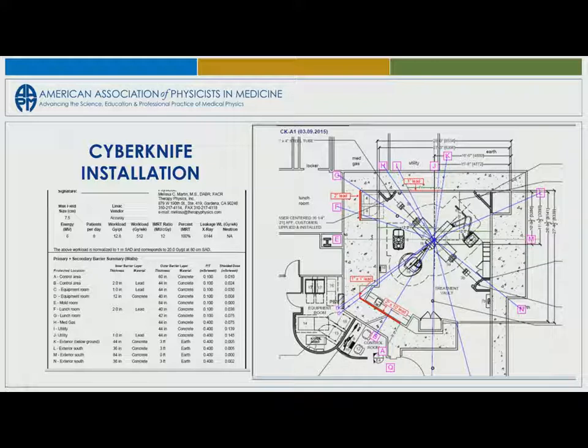CyberKnife installations - this is the one in Alaska, I think, where they converted what was a CT simulator, not a CT but the Varian version of the traditional simulator. They had a traditional simulator in this room and took it out to put in a CyberKnife. So you can make strange conversions, but it worked. That's the only way they could fit it in, was to put it at an angle. So it's in there, with your primary barriers ending up here and then around the side.